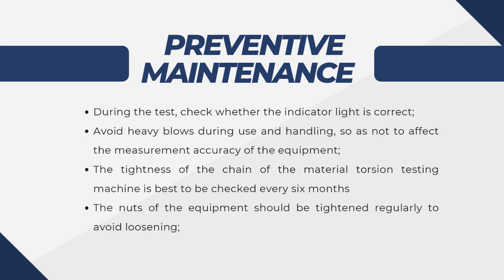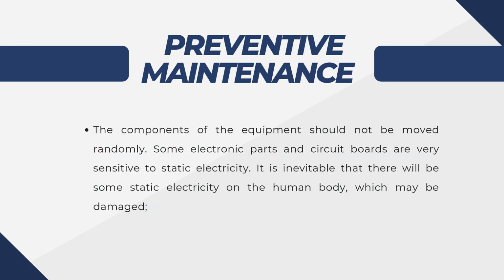Preventive maintenance. During the test, check whether the indicator light is correct. Avoid heavy blows during use and handling so as not to affect the measurement accuracy of the equipment. The tightness of the chain of the material torsion testing machine is best to be checked every 6 months. The nuts of the equipment should be tightened regularly to avoid loosening. Moreover, the components of the equipment should not be moved randomly. Some electronic parts and circuit boards are very sensitive to static electricity. It is inevitable that there will be some static electricity on the human body, which may cause damage.